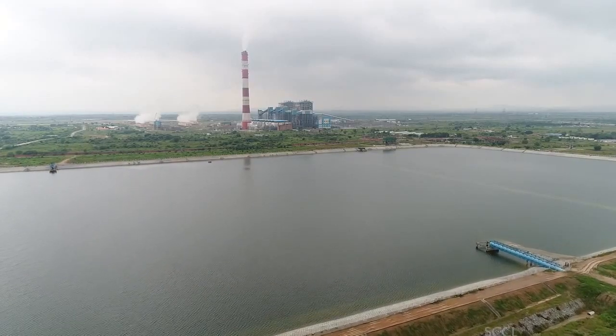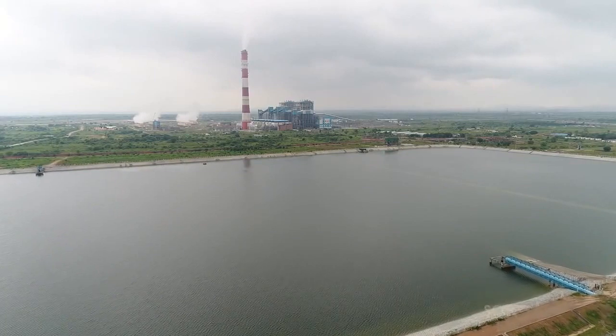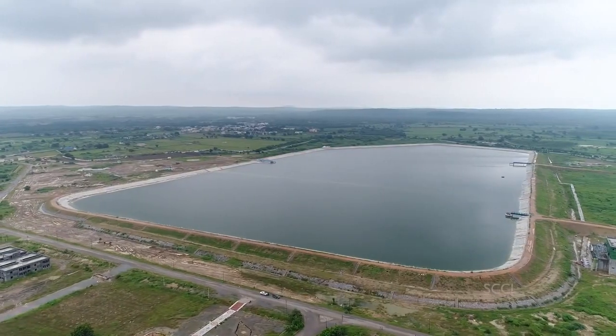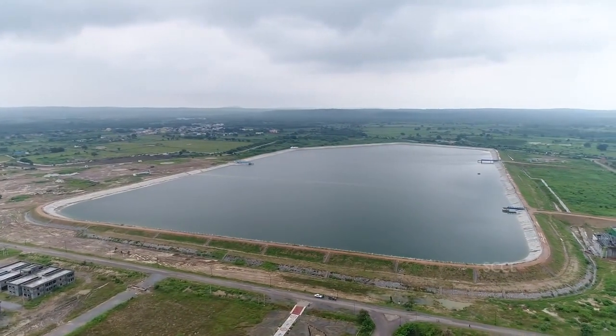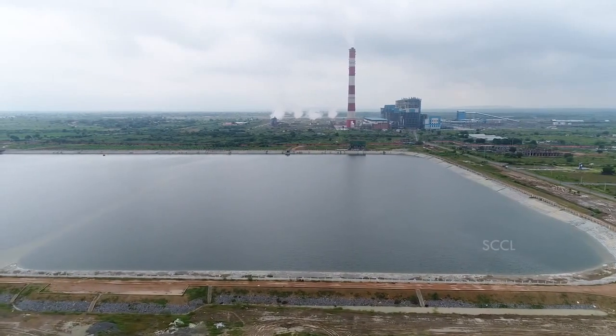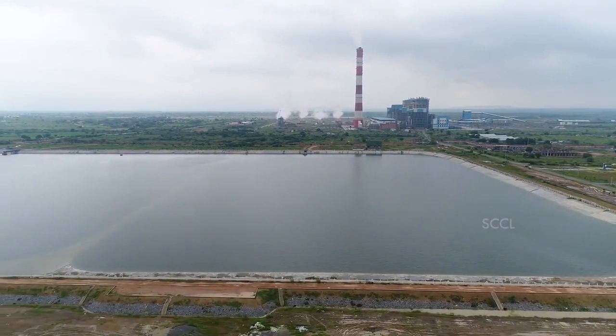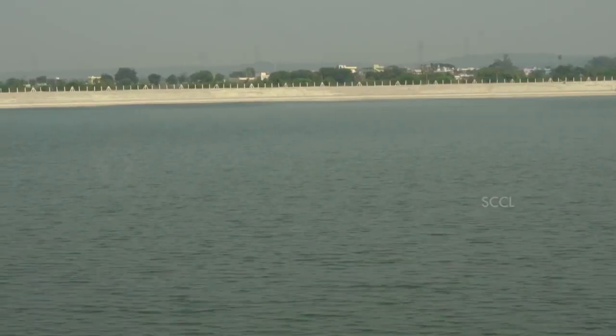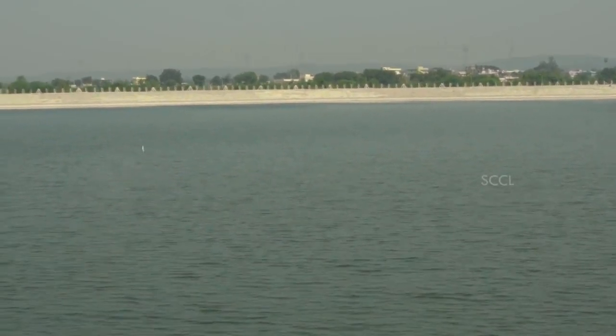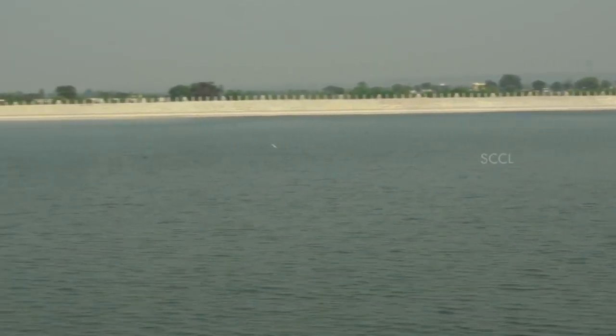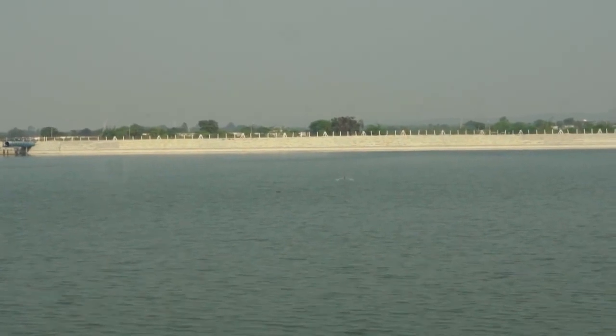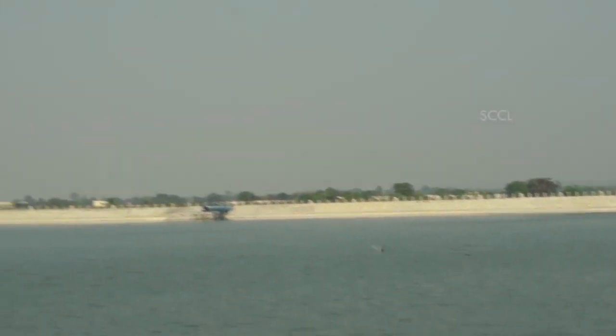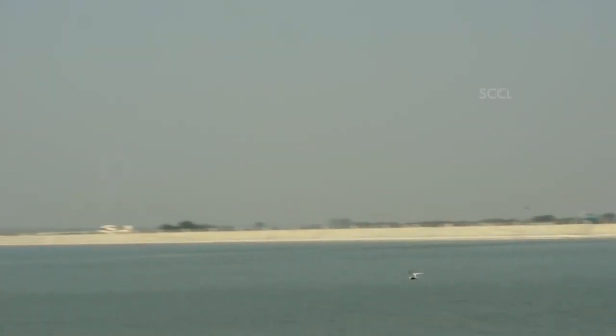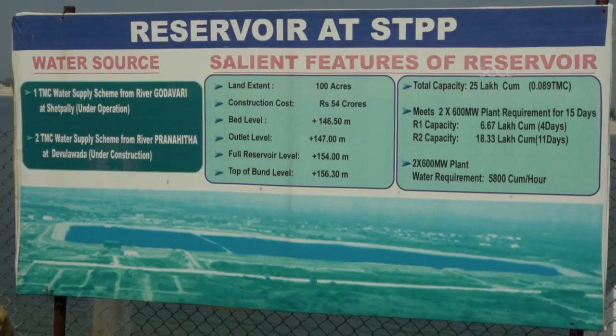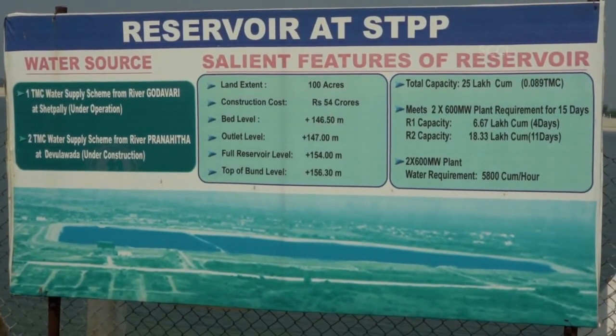Water is another primary requirement in power generation. STPP is having two sources of water. 1 TMC of water from river Godavari and another 2 TMC is being drawn from river Pranahita. Raw water is stored in a water reservoir. The reservoir's capacity is 25 lakhs cubic meters, which is sufficient for 15 days of plant operation.